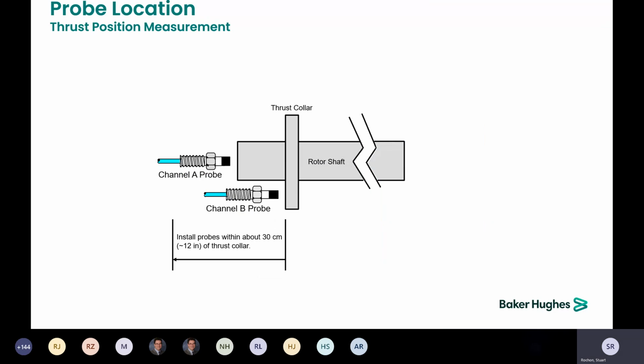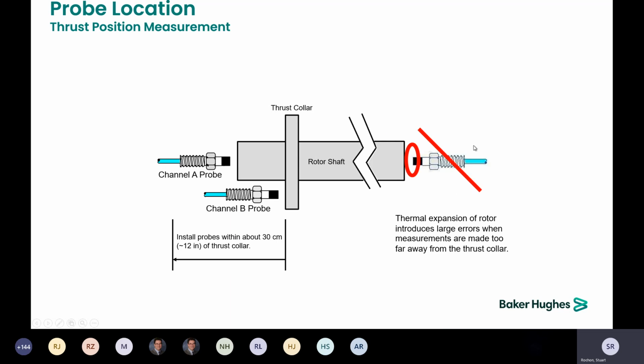For thrust, we recommend that you install the probes within 12 inches of the thrust collar. Best practice is to have it actually on the thrust collar, but in some cases that is just physically not possible. But as long as you get it within 12 inches, generally we don't run into a problem. However, if you put it further away, say on the other end of the shaft, you can get into thermal expansion issues. And if you're fighting how the rotor's thermally expanding versus actual thrust movement, it really makes it hard to comprehend what's actually going on with the thrust.